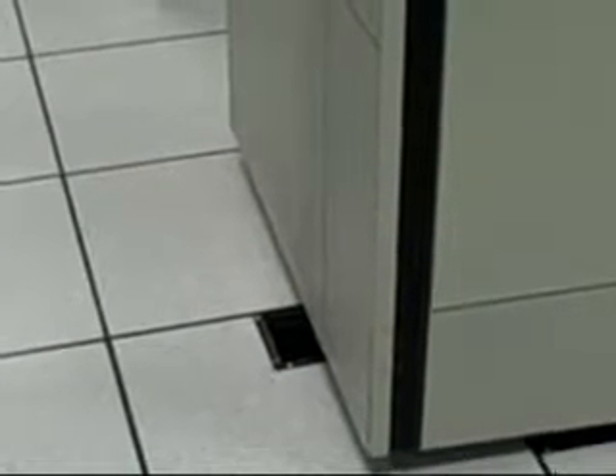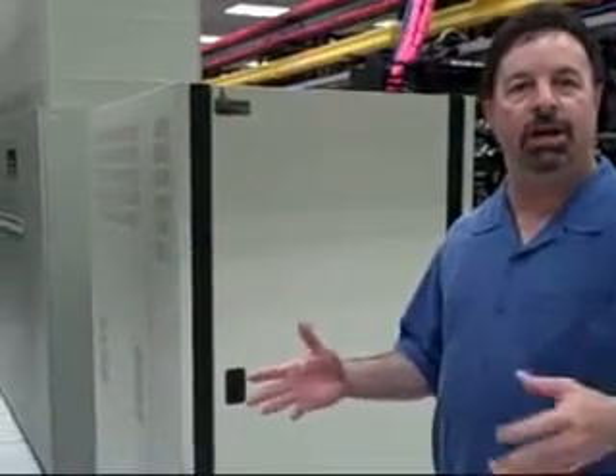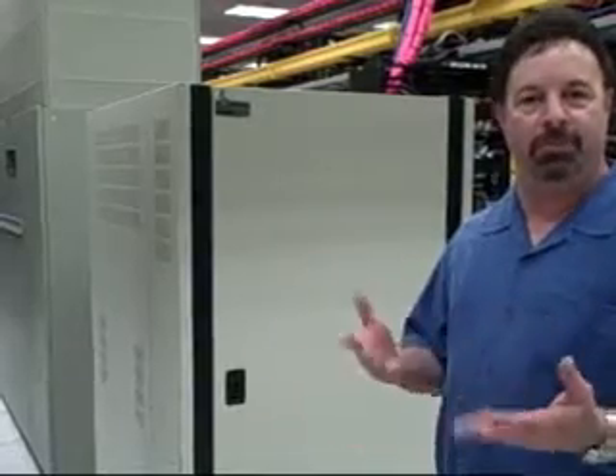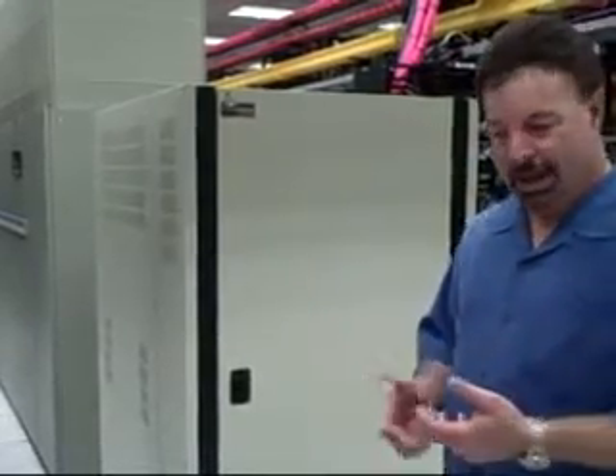Sometimes there's no avoiding having a hole in the raised floor, such as with this power distribution unit, but Jeff has still managed to minimize bypass airflow. So on some of our older power distribution units where we have the cabling coming out under the floor, the holes were an irregular size. There really wasn't a product, like KoldLok or something like that, that would help us prevent that airflow. So what we did is we used a product, Pleniform. We were able to actually, under the floor, build a dam around the PDU and just have cutouts in it where the actual electrical cabling is cut out, effectively blocking any of the airflow to come up through the bottom of the PDU.